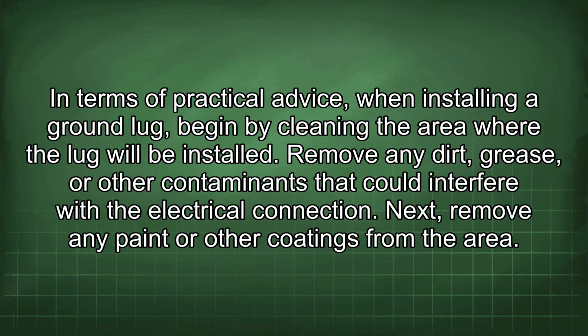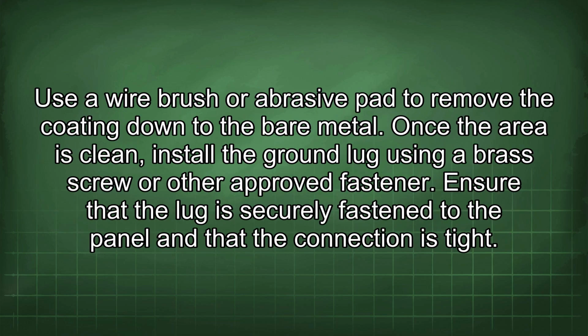In terms of practical advice, when installing a ground lug, begin by cleaning the area where the lug will be installed. Remove any dirt, grease, or other contaminants that could interfere with the electrical connection. Next, remove any paint or other coatings from the area. Use a wire brush or abrasive pad to remove the coating down to the bare metal.